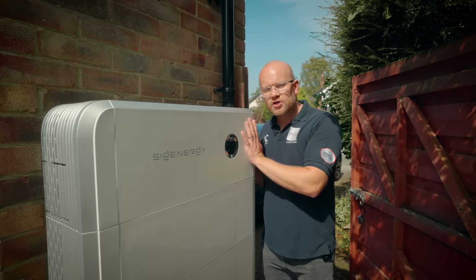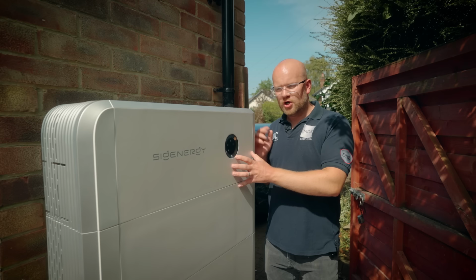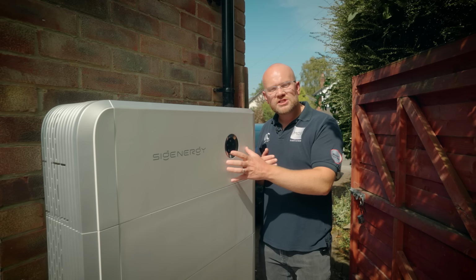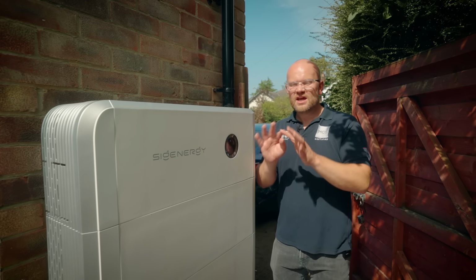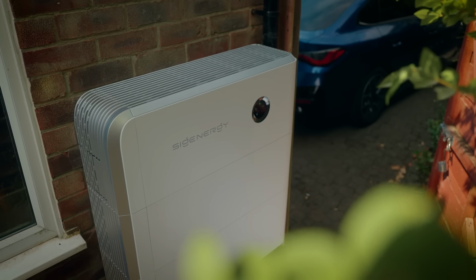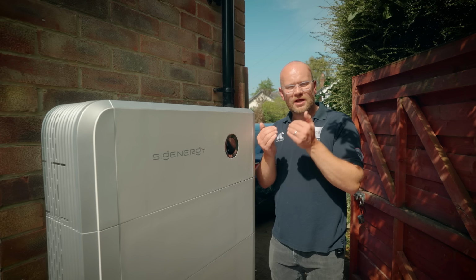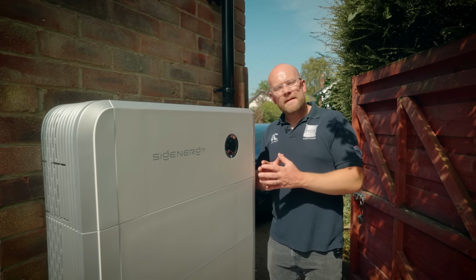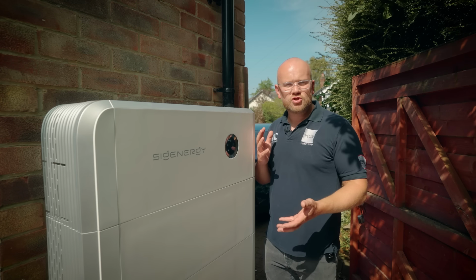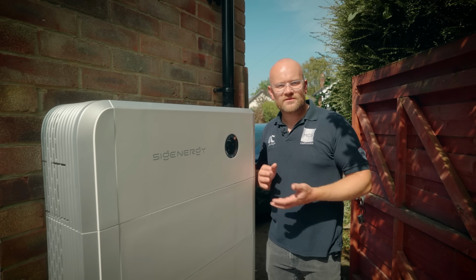One thing to note about these SigEnergy inverters, as I mentioned earlier on, they come in a range of 3 to 12 kilowatts in a single phase version, is that if we picked a larger inverter like we've got in this scenario, 8 kilowatts, which is on the bigger side, when we put the application into the DNO, which is called a G99 application, they may restrict what you can export out to the grid. Because these are G100 compliant, effectively, we can generate the energy locally on your roof, store it in the battery storage, use it in the home, and if the grid needs a restriction in any way, so throttling the generation down at any point in time, you can set that up. What that means is we can pick a bigger inverter with more battery storage without having to reduce the size of the system that we've got installed.